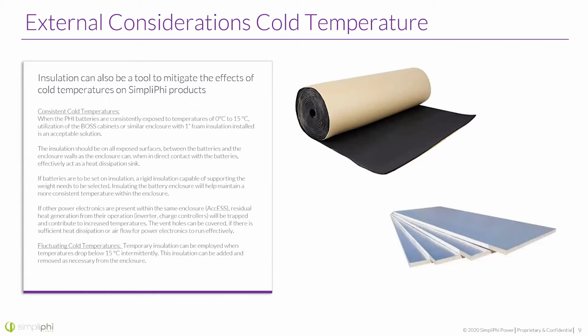But the idea is the insulation should be on all exposed surfaces between the battery and the enclosed walls. And really, when in direct contact with the batteries, it can act to keep that heat in. It's basically a heat dissipation sink. And it's just really simple stuff here. Maybe you have an enclosure, it's outside, but you think your temperature is going to hit, let's say, 0 degrees Celsius every now and again.